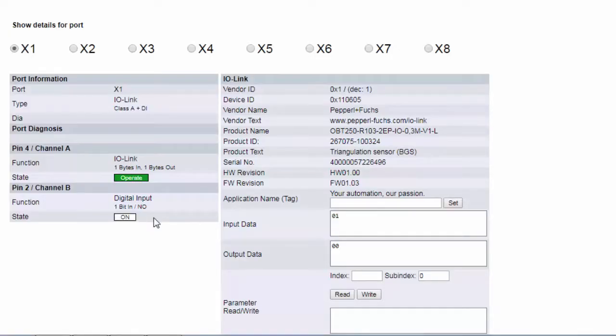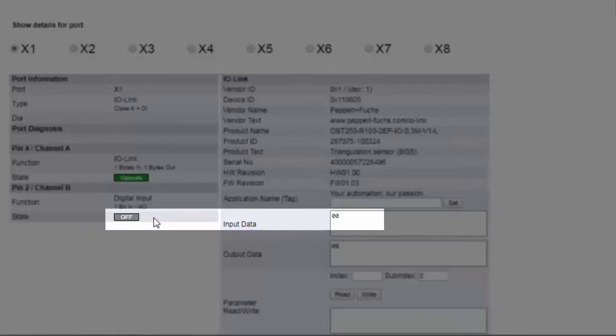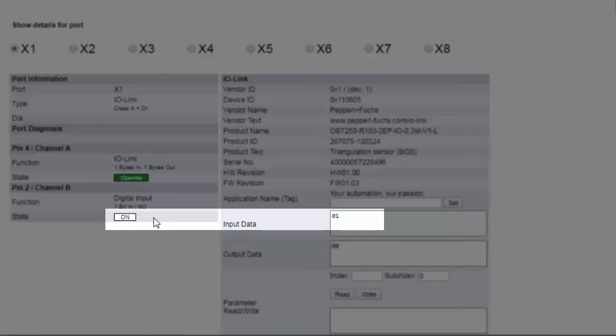As the sensor gets blocked, we observe the on-off status change. In addition, we are seeing our process data toggle on and off as well. Note the input data as 1 here and 0.